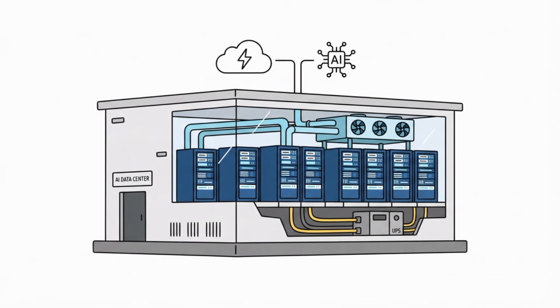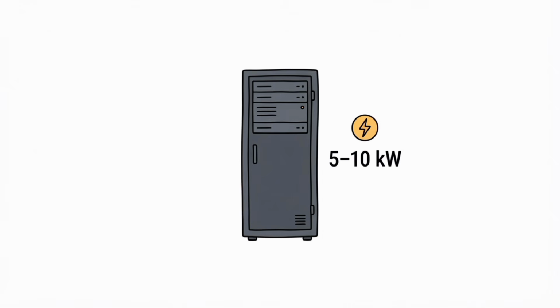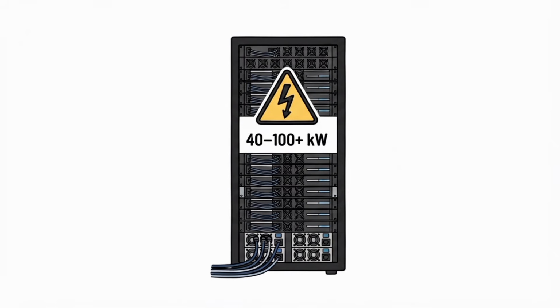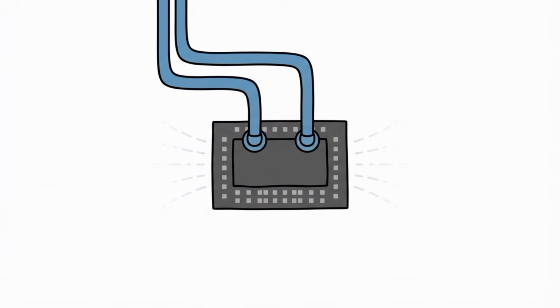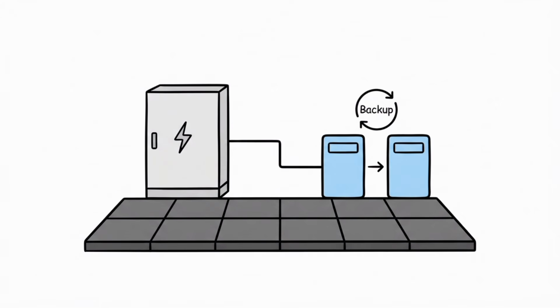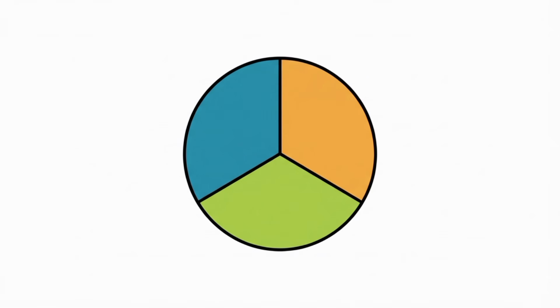An AI-optimized facility is not that building. A conventional server rack pulls 5 to 10 kilowatts of power. A rack packed with NVIDIA GPUs pulls 40, 60, sometimes past 100 kilowatts — closer to what you'd expect from an industrial furnace than an office park. Central air can't pull that heat out fast enough, so the industry moved to liquid cooling piped directly to the chip. That single change cascades into reinforced flooring, a completely rebuilt electrical distribution system, and redundancy requirements that barely existed 5 years ago.